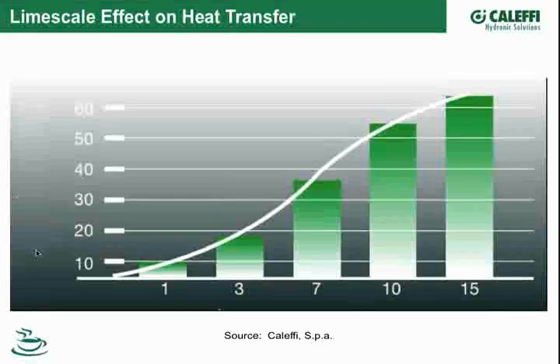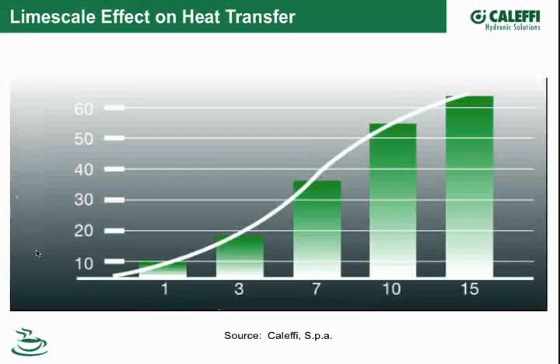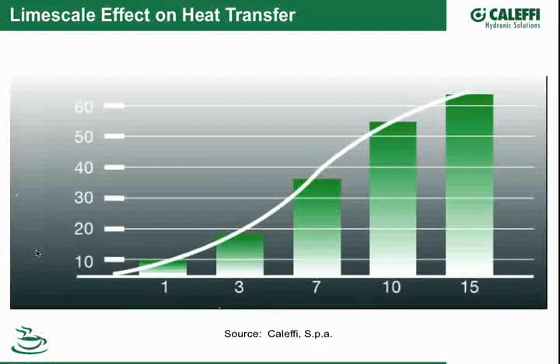This one here I put in, this was a slide that we used for some other thing, but it really shows any kind of buildup inside a pipe or a heat exchanger, whether it's a boiler or even a heat emitter, a panel radiator, a radiant tube, or anything that has to transfer the heat through the fluid in it. If you get a buildup on the wall of that tubing or the wall of that heat exchanger, it doesn't take much of a buildup before you start hampering your heat transfer ability. So if you've got a boiler with a big burner in it and you're trying to get the heat from the burner into the fluid that's in there, and you've got a coating of glycol that's caked in there because it's been burned because you didn't have flow rate or something through it, you're going to take a hit, not only the glycol going bad and causing problems, but also the heat transfer when it's in there trying to do its job. So it's kind of a double whammy there when things start to go bad with fluids if they start coating out.